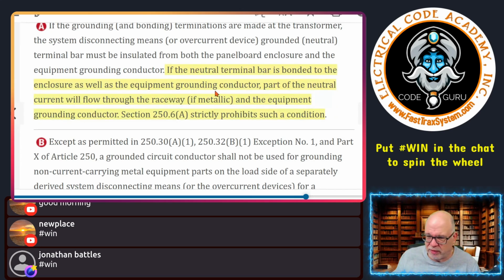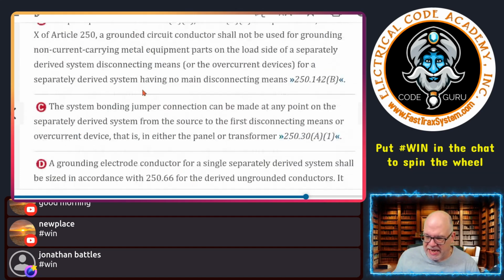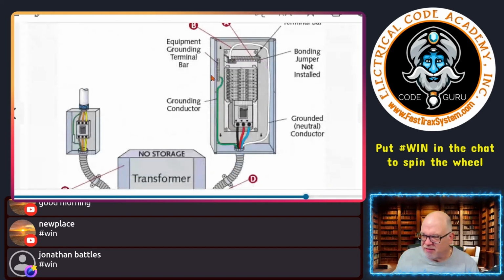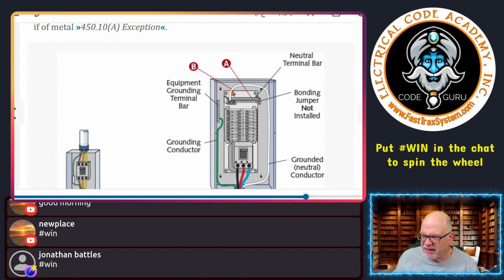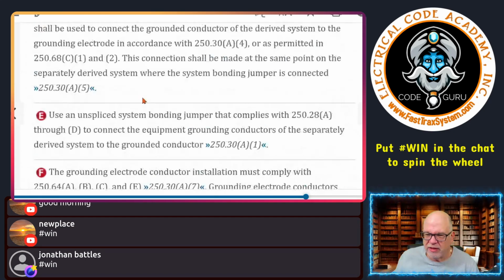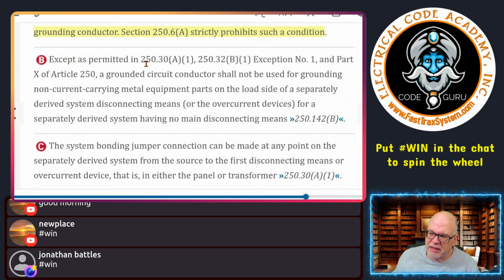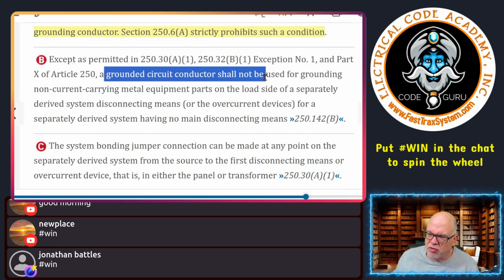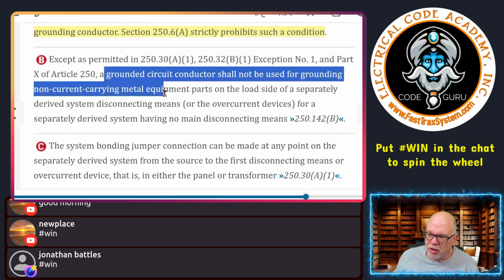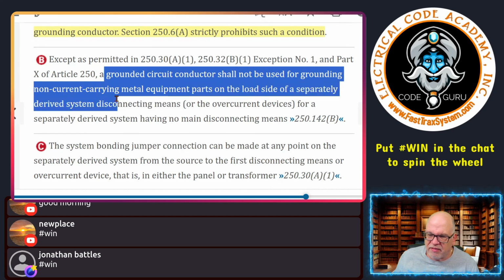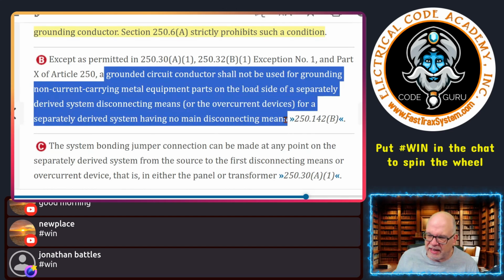Okay, so we're prohibited from doing that. Now, B is talking about right here. Okay, so we got B right here. And let's see what it's referring to. It says, except as permitted in 250.30(A)(1), 250.32(B)(1), exception 1, and Part 10 of Article 250, okay, except as in those permitted allowances, it says a grounded circuit conductor shall not be used for grounding non-current carrying metal equipment parts on the load side of a separately derived system's disconnecting means, okay, for a separately derived system having no main disconnect, okay?